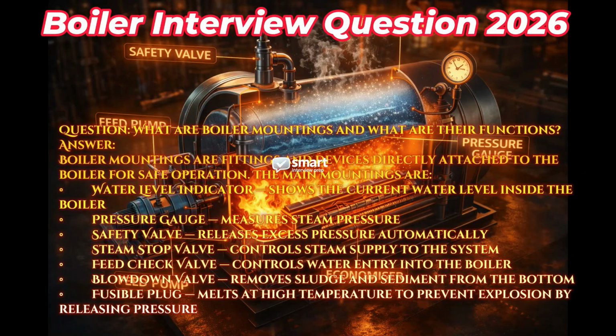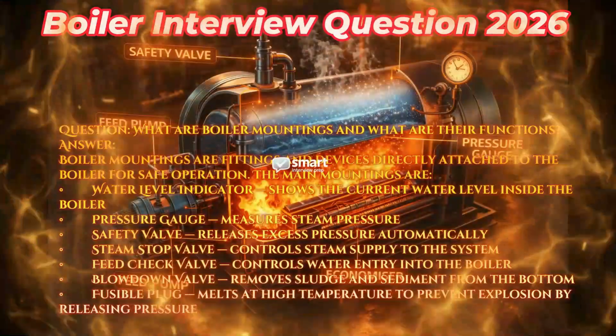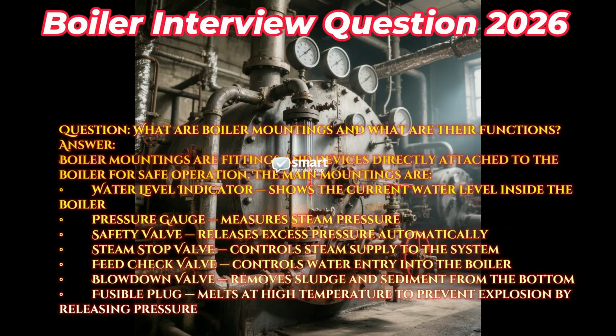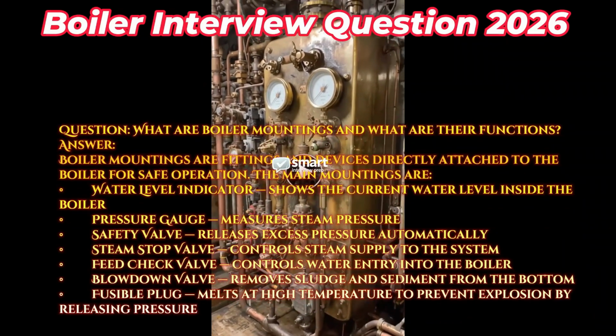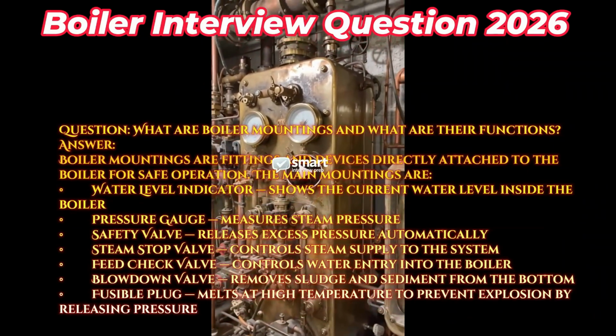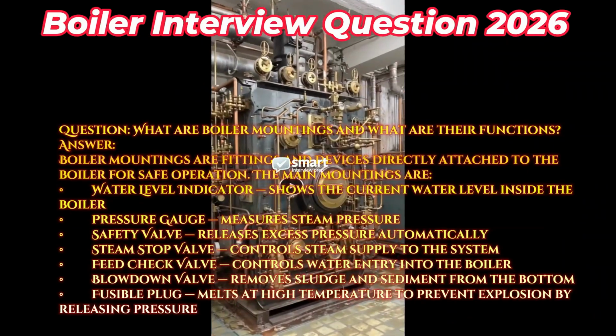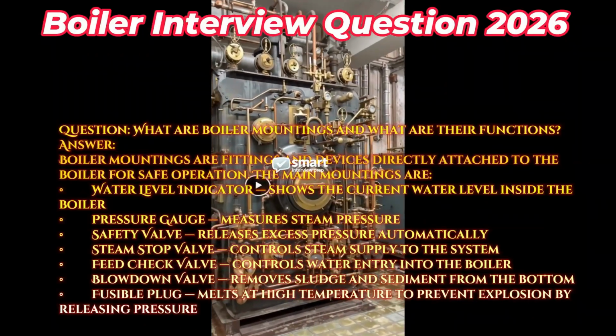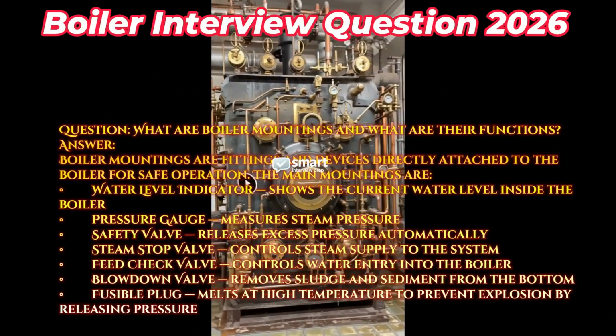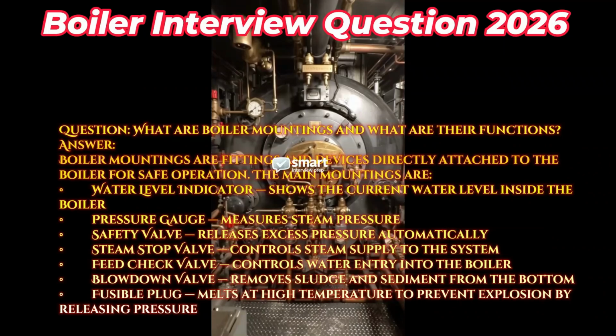Question: what are boiler mountings and what are their functions? Answer: boiler mountings are fittings and devices directly attached to the boiler for safe operation. The main mountings are: a water level indicator, shows the current water level inside the boiler. Pressure gauge measures steam pressure. Safety valve releases excess pressure automatically.